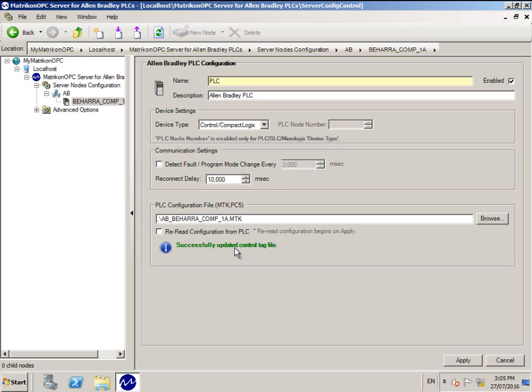Also, at the bottom of the window you will see successfully updated control tag file in green. This indicates that the PLC was browsed and a point validation file was automatically built.